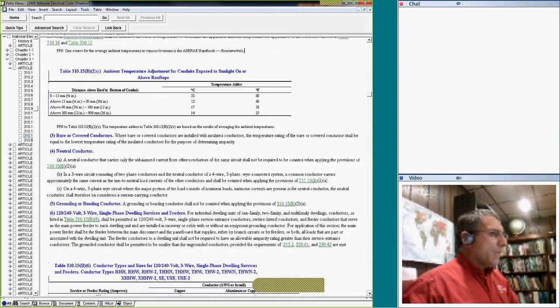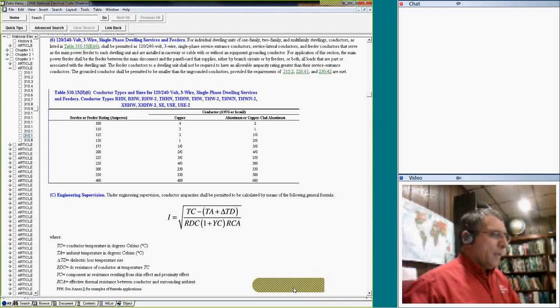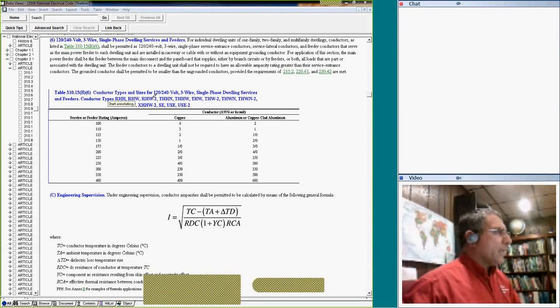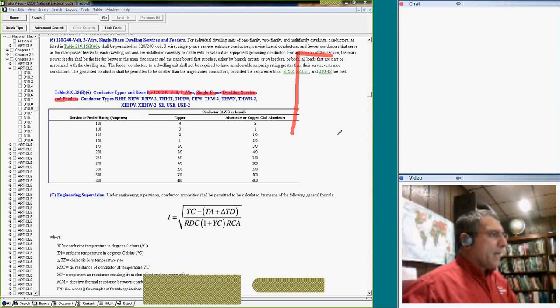Moving on, so we know how to use these two tables before we move on. Okay. Conductors, I'll emphasize this table, guys, as basically for residential. So I always want to highlight, make sure if you're doing residential, it's 120/240. It has to be 3-wire. It's single phase. It's for services and feeders only. So this table, suppose I have a panel, guys, here's my panel. My overcurrent protection device in this panel right here, let's just say it was a 400 amp, and then you find a conductor that can feed this panel. Here's my 400 amp, and it's listed as copper, so that will be 400 kcm. 400 kcm.